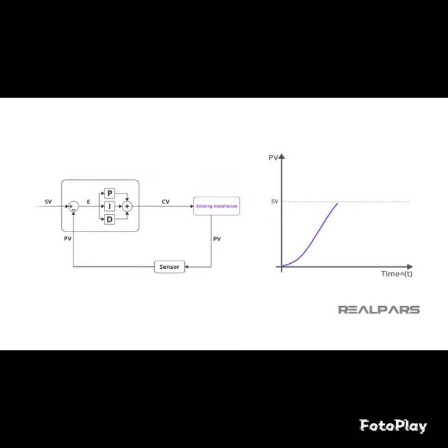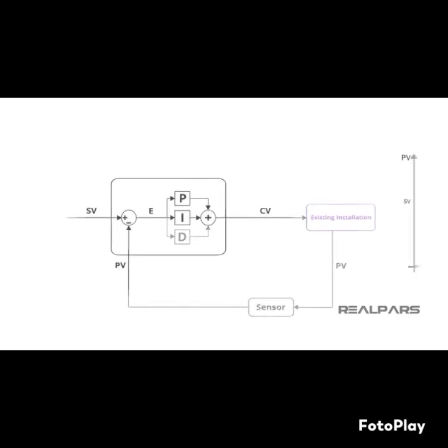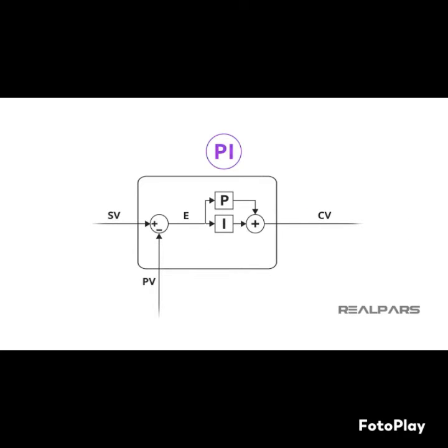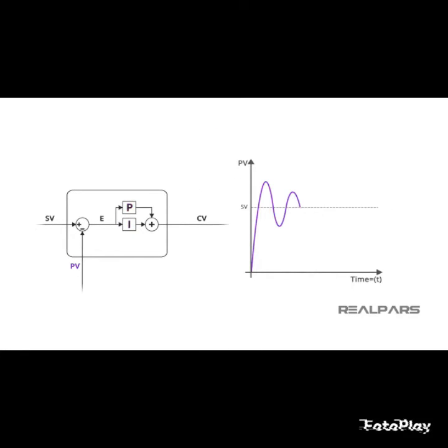Because the PI controller is the most widely used, we will only be adjusting those parameters. As we have discussed the differences in measurements in the PID terms, for this tutorial, we are going to standardize on gain and repeats per minute. To just jump right in, if your process variable changes quickly to changes in your control variable, you will start with a low gain, possibly as low as 0.1, while adjusting your reset between 1 and 10 repeats per minute.